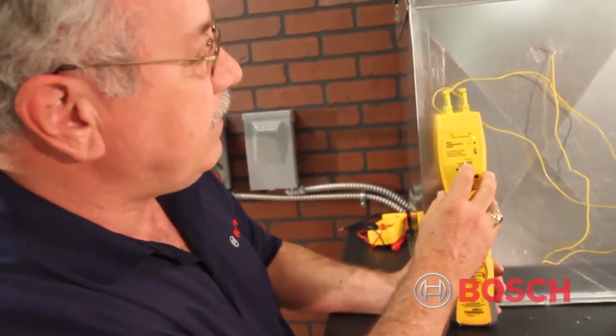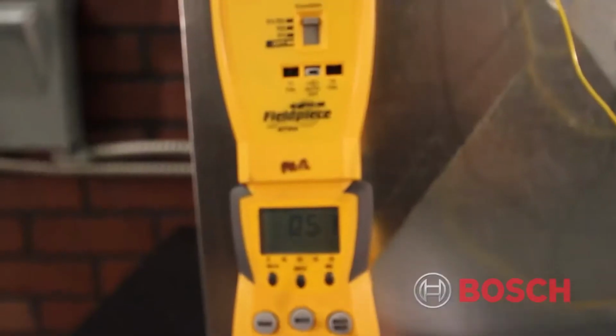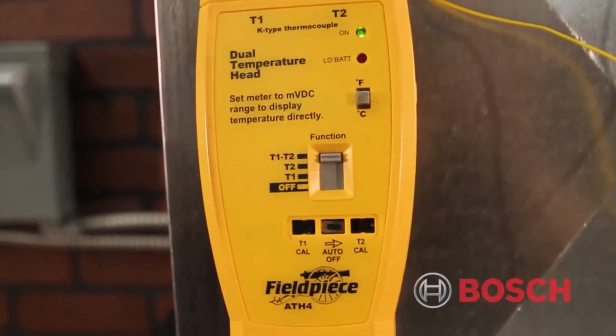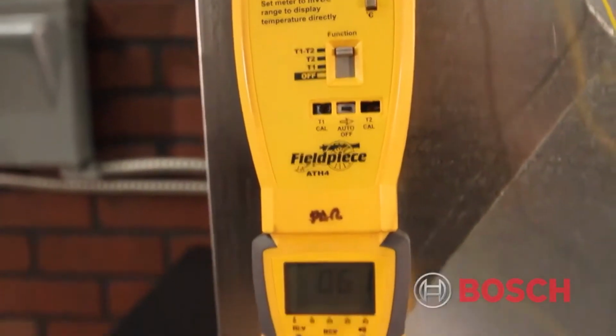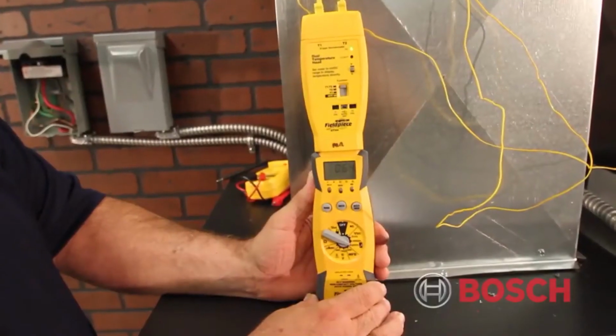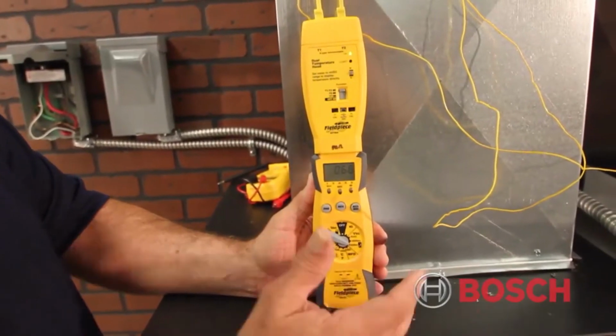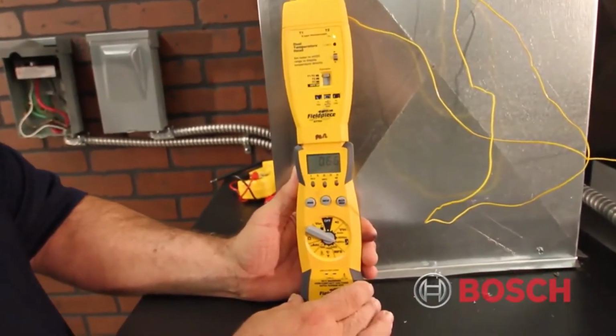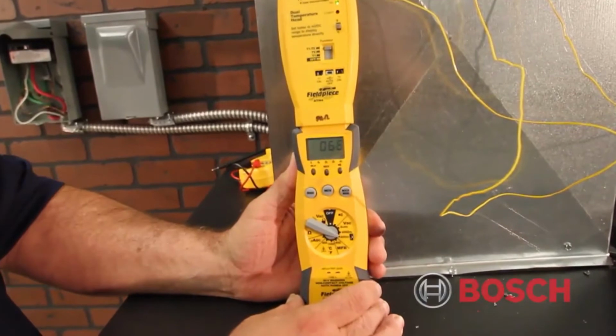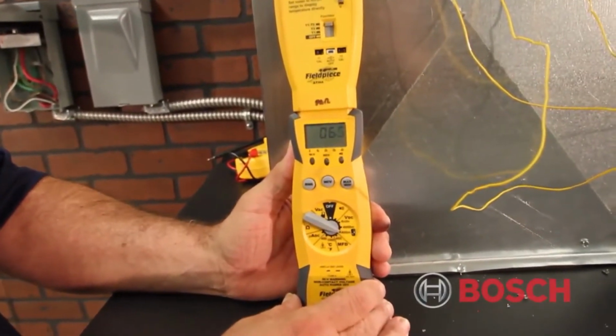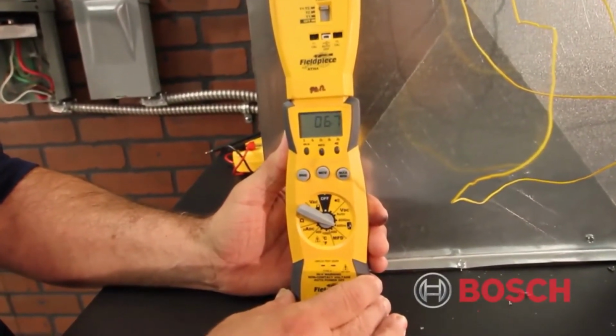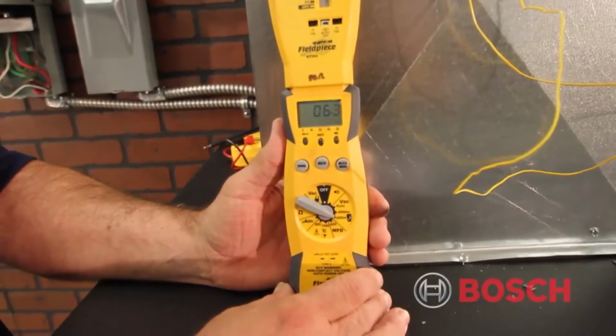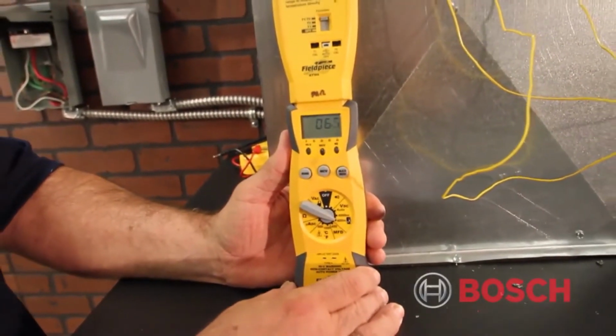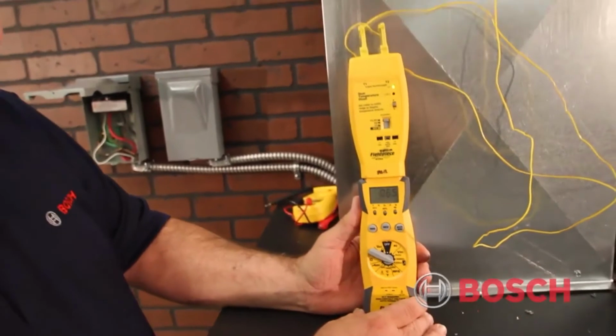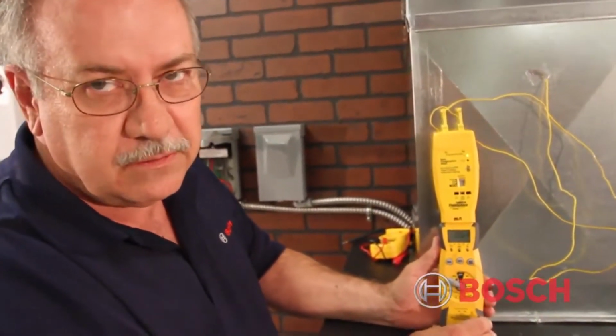This particular device has a function key that allows me to determine the difference in temperature, which is what I'm after. I want to find out what the largest spread is before it starts overheating or tries to satisfy. So right now we are in the 6.5 degree range, approaching probably 7 degrees. Of course, this is dependent on the size of the heater. This is probably a small heater, and I would expect probably less than maybe 10 degrees difference in temperature.